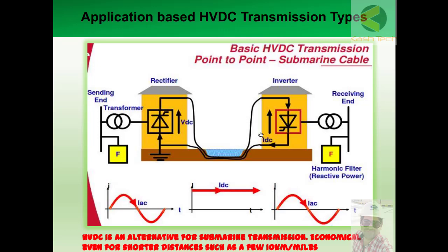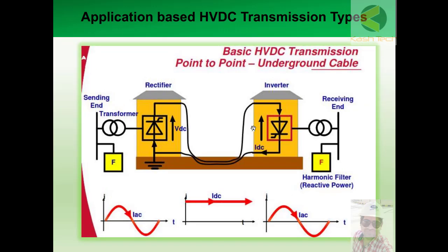HVDC is an alternative for submarine transmission and is economical even for short distances such as a few tens of kilometers or miles. Based on feasibility studies, for submarine cables you only need to lay one or two conductors for HVDC, which are smaller conductors. The cost becomes very high if you use AC transmission under the sea, even for shorter distances, making HVDC the cheaper option.